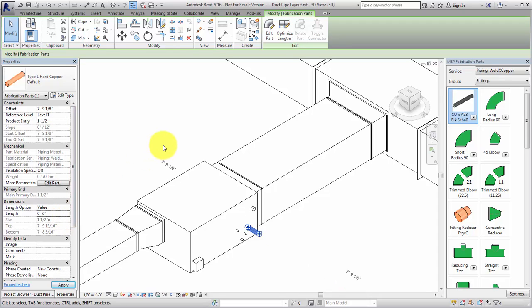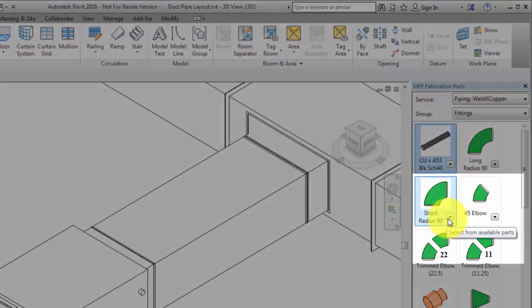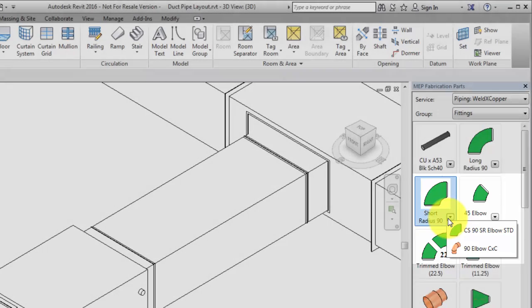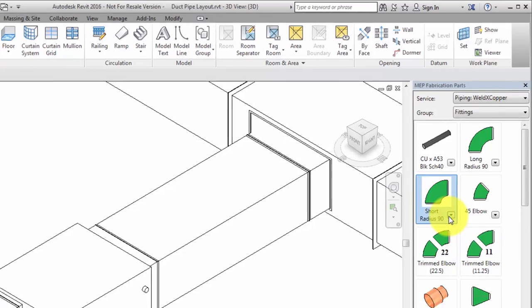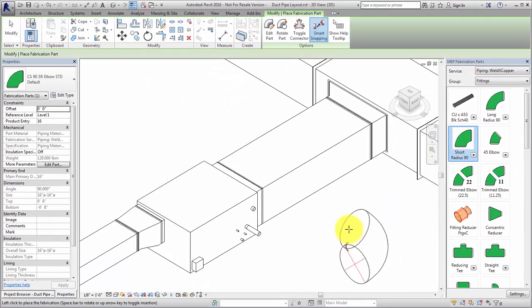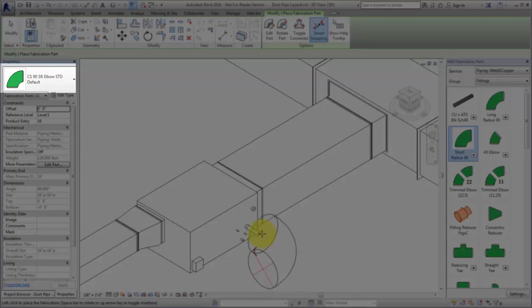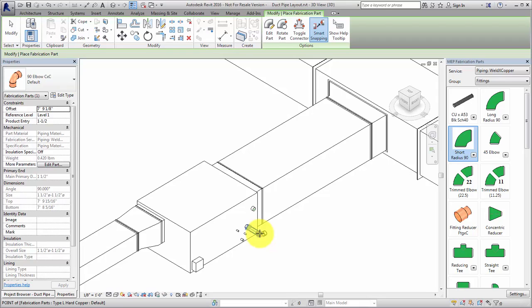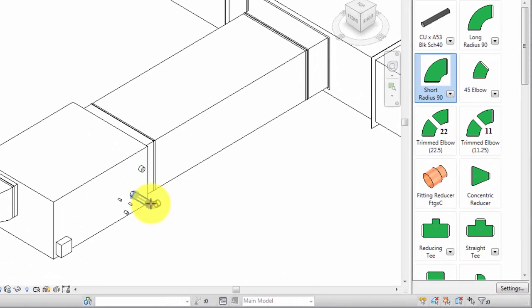Select the Short Radius Elbow and notice that it displays an arrow. This indicates that different parts are available depending on the size. For example, one material is used up to a certain size elbow and a different material is used above that size. In this example, the copper elbow is automatically placed. Press the space bar to rotate the elbow in 45-degree increments.